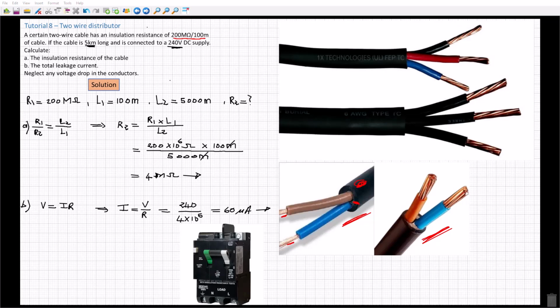So you will be probing and looking all over the place. What is going on? Well, the problem is lying with your cable. It's leaking current that is high enough for your leakage circuit breaker to detect it. So this is why it's very important to know the insulation resistance of your cable before you spec it to use in any application.